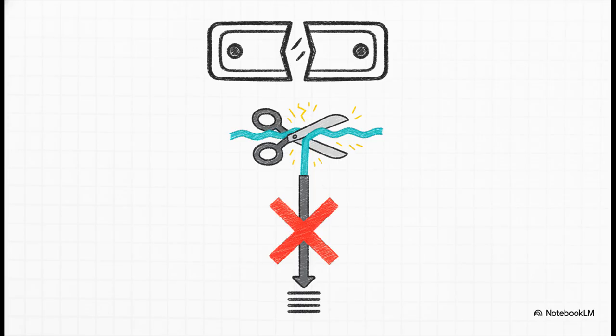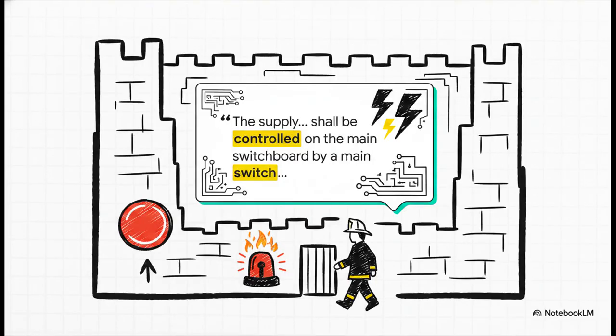Why? Because that earth connection is your absolute vital lifeline. It gives fault currents a safe path to escape into the ground instead of traveling through a person. If you cut the earth, you are quite literally disabling your ultimate safety net. And this brilliantly illustrates the whole concept of the master kill switch. The standard states, the supply to every electrical installation shall be controlled on the main switchboard by a main switch or switches, because every fortress needs a way to pull up all the drawbridges at once.